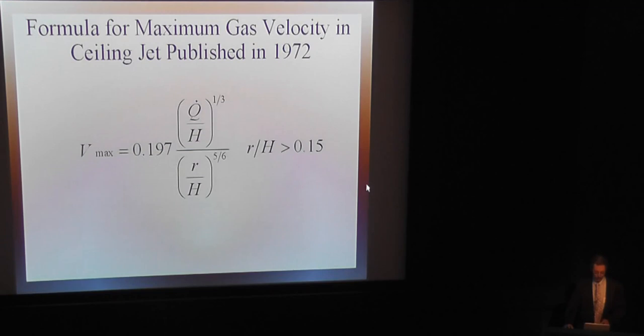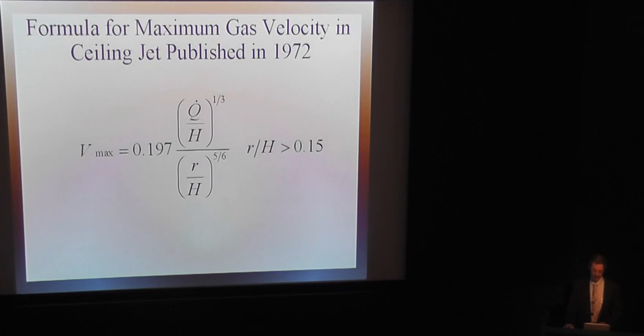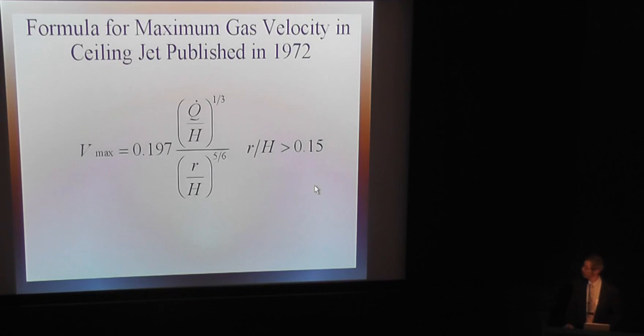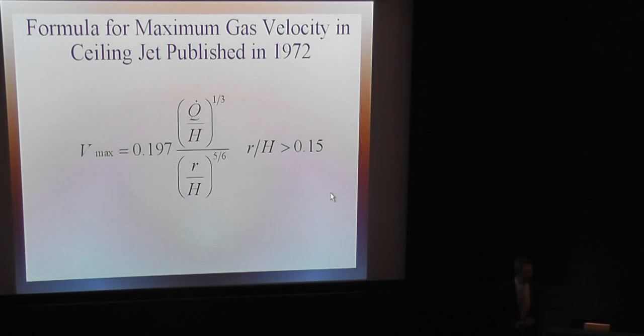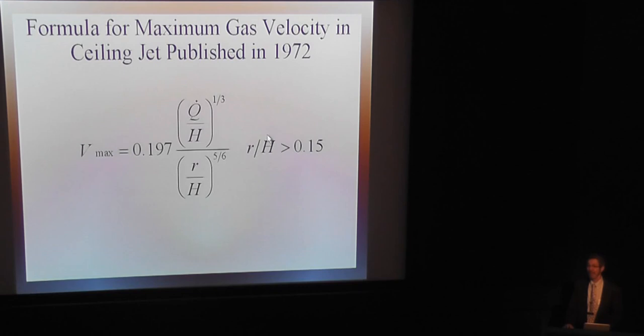These are the formulas that were originally published, in SI units — kilowatts and meters. This is the formula for the maximum ceiling jet velocity, the radial outward velocity on the ceiling. The formula is valid from where the turning region ends, at radius over ceiling height greater than 0.15. Q-dot here is the actual heat release rate of the fire, though at that time we didn't know exactly what the heat release rate was — we were guessing from mass loss data. We now know that velocity is controlled by the convective component of the heat release rate.